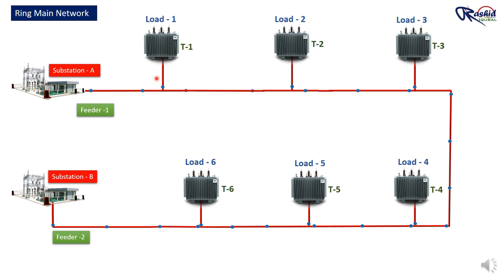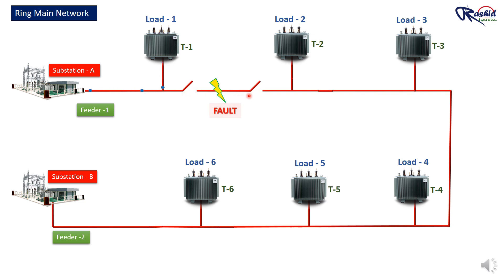We can simply add switches and circuit breakers to control and protect the system. For example, I can install switches between the load and feeders, and also add a circuit breaker or load break switch with fuse to protect the transformer. As shown here, all transformers are getting power from substation A through Feeder 1. If there is a fault in Feeder 1 between Transformers 1 and 2, we can fix it by turning off the breaker on both sides of the fault section, which safely disconnects the faulty part so that the technician can work on it.